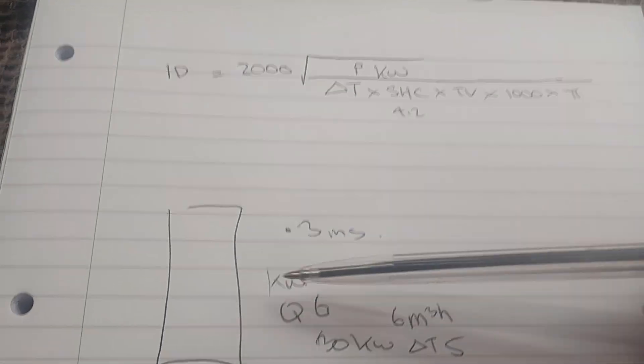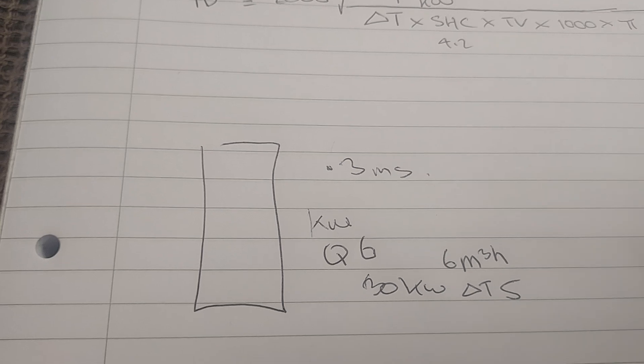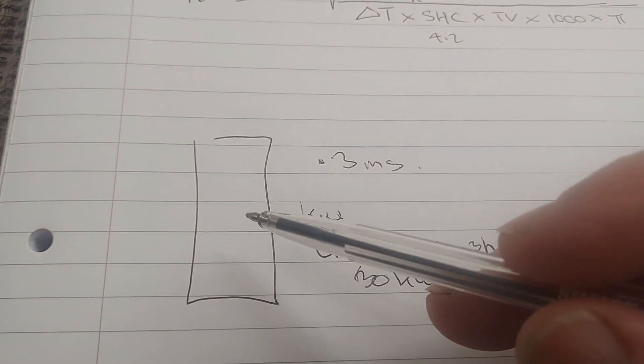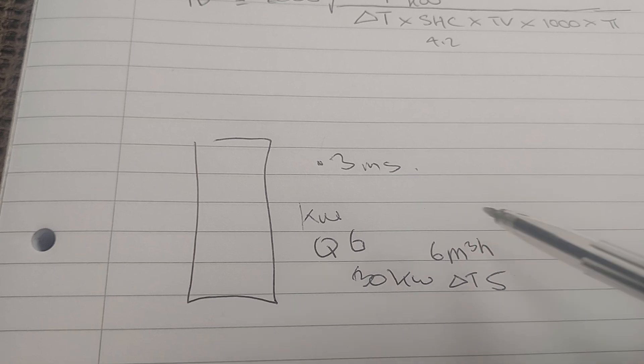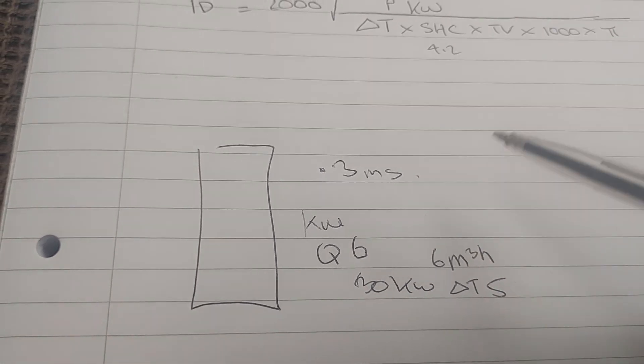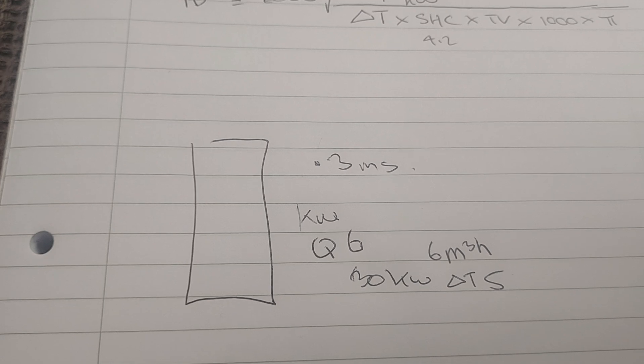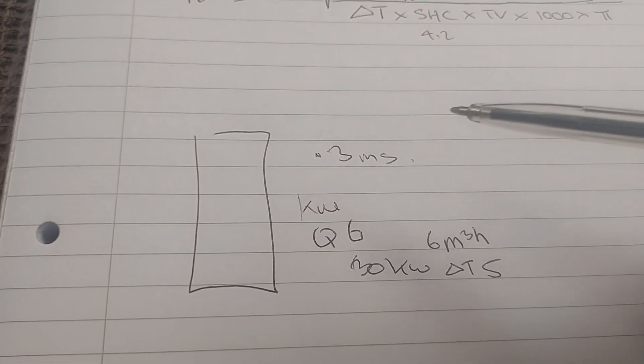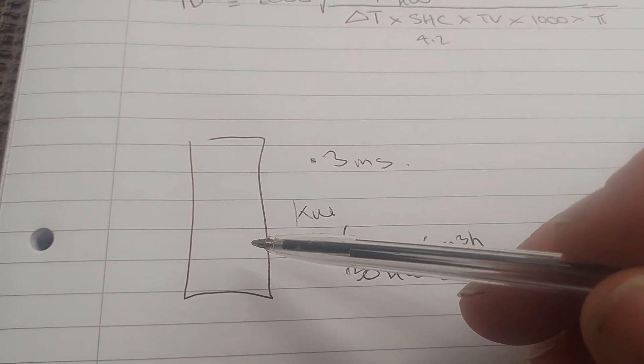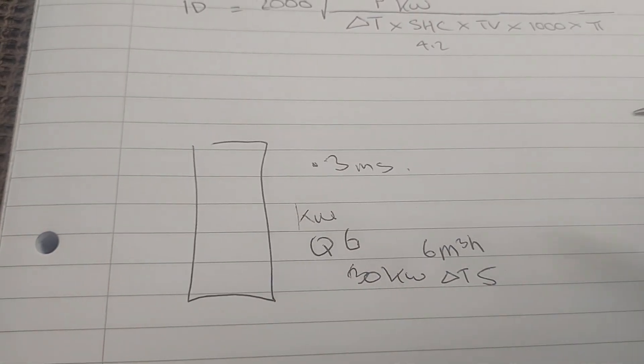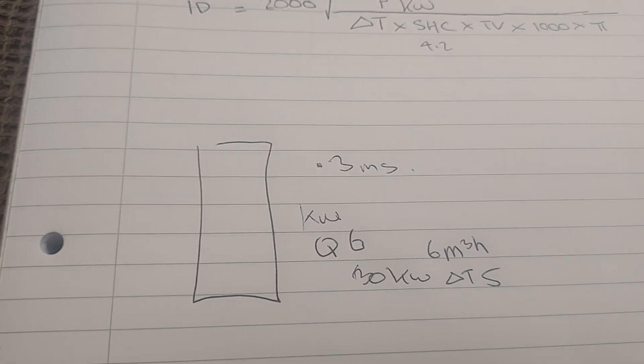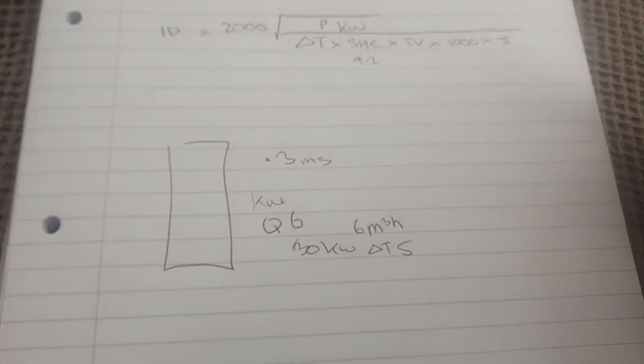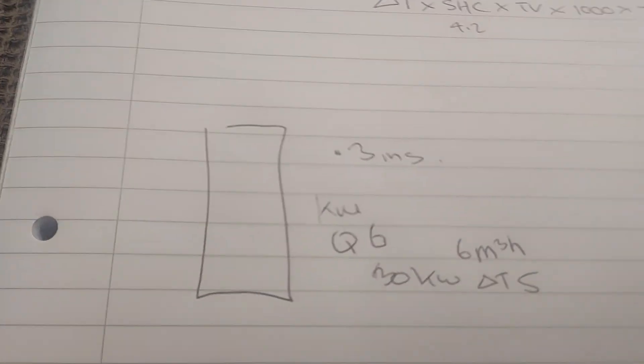So if you were designing a low loss header to make it yourself from pipe, you would just simply use the formula, put in the 0.3 and it would tell you what diameter tubing to use. Just a quick one on low losses: if you do a low loss header horizontal, you must feed it from the bottom, don't feed it from the top. There's a video on my YouTube explaining why. Another little rule for low loss headers is a low loss header actually forms a mixer. It works the same way as a mixer but it's not variable temperature.